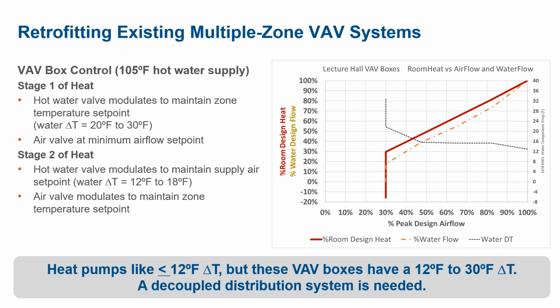I show this graph to highlight what Sarah said earlier about requiring decoupled systems. Most heat pumps like a delta T less than 12 degrees at the condenser. However, the VAV boxes are 12 to 30 degree delta T, so a decoupled distribution system is needed for the VAV and fan coil systems that were discussed earlier.